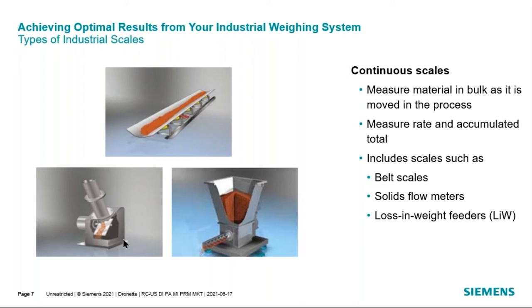Solids flow meters are also considered continuous scales. The most common type is an impact flow meter. Material gravity-feeds through a pipe — typically powders or granule-sized materials — and strikes a sensing plate. The force of impact is measured and used to calculate how many tons per hour or pounds per hour are going through the flow meter at that moment. You would also accumulate a total on that.